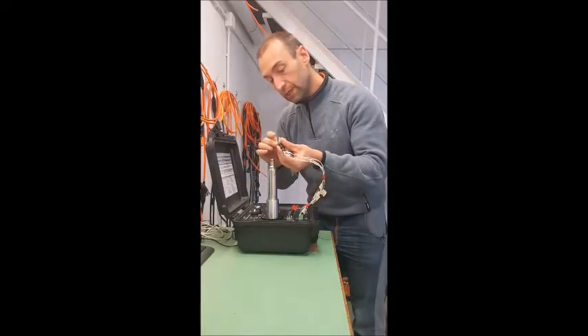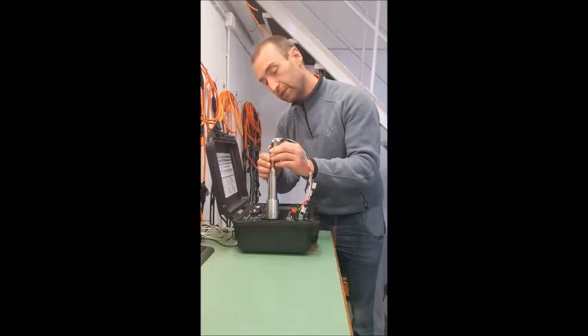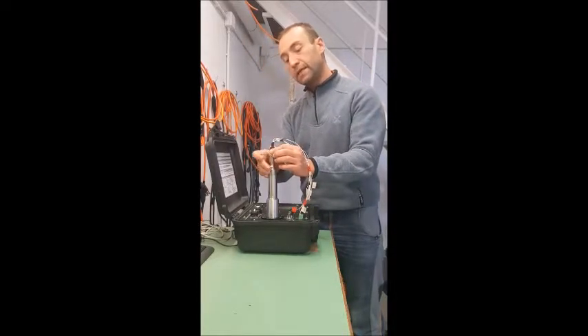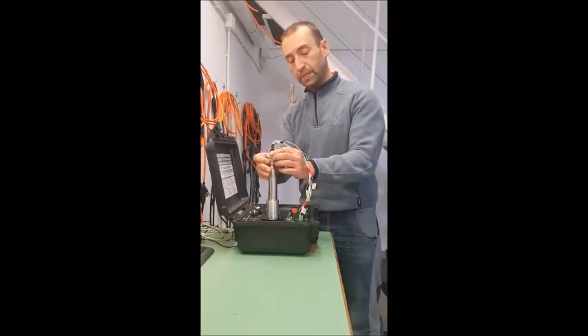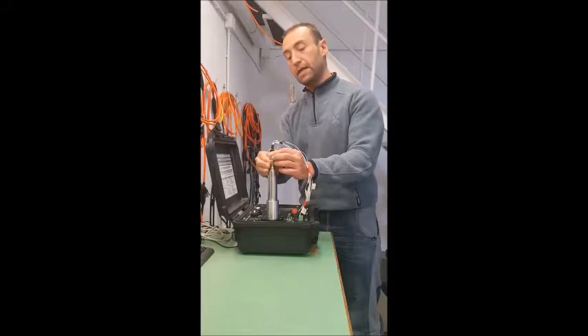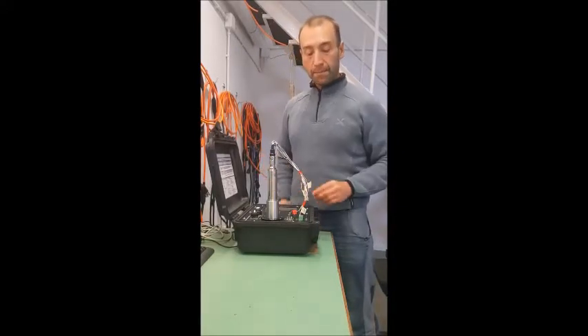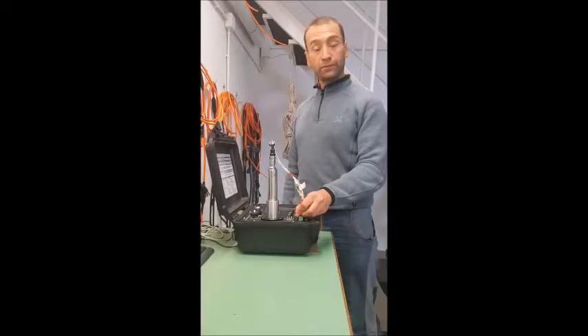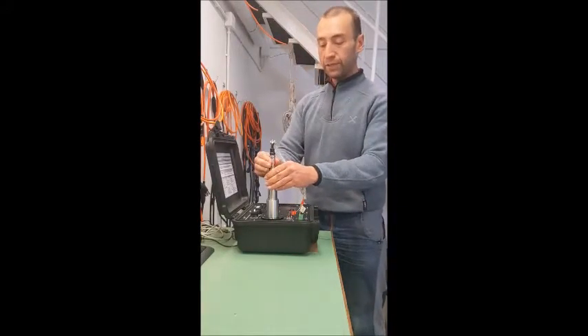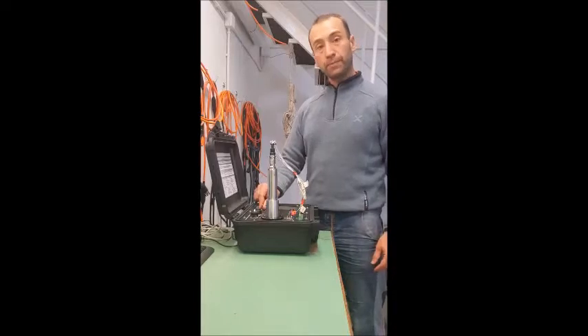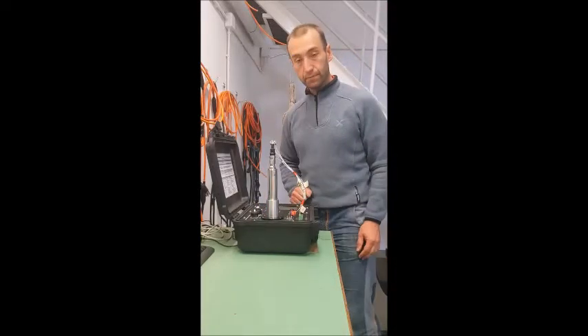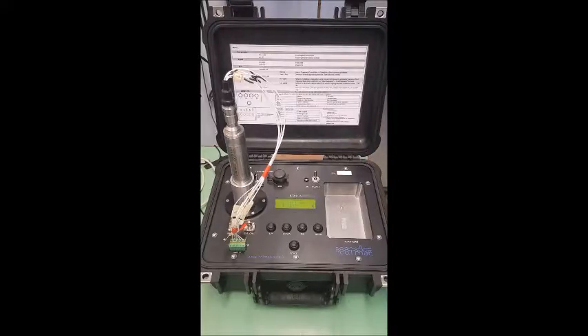So each time you connect a hydrophone, you also need to connect a cable to the hydrophone that provides power supply and reads the balanced output from the hydrophone. Once the hydrophone is connected, power can be given. This you are seeing now is the interface of the calibrator. First off, we have a power button, like we said. This button can be used to switch the device off and on.